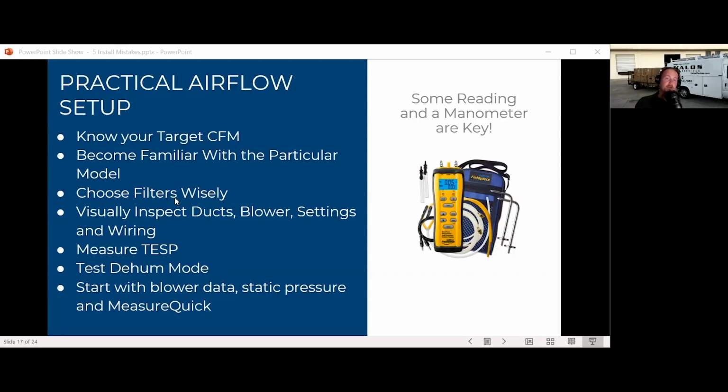Because if they set a target that's too low, or say they have a dehumidification terminal and it's not energized, so it's in dehumidification mode and running a lower fan speed while they're testing, or they only have a Y call versus a Y2 call, and so it's only running 60% of its designed airflow, they're going to see low static and they're going to think that the system's working good because they see low static. But you have to hit the target first. So we have to make sure that installers are trained appropriately on how to wire and set up this equipment.